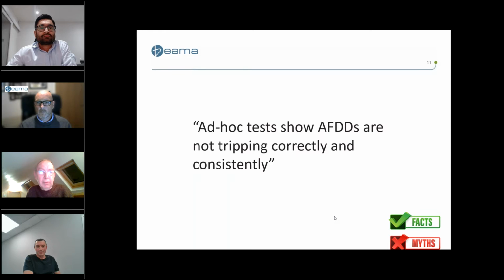Now, product standards establish a common and repeatable set of tests to demonstrate product performance, and those are essential. So there's a common set of rules, if you like, used by manufacturers. Failure to test according to the product standard will produce inconsistent and erroneous results, which will certainly be misleading. You could look at some of these tests online and think, oh, the AFDD isn't working. Well, they haven't been tested correctly. So it's essential that correct testing is undertaken. Otherwise, you will get those erroneous results.